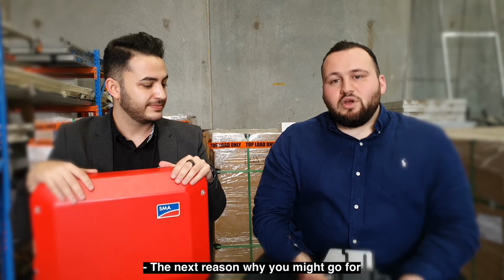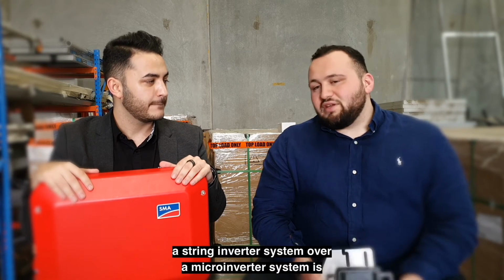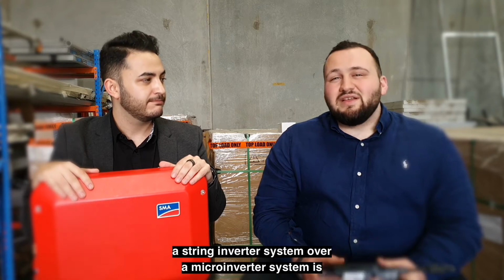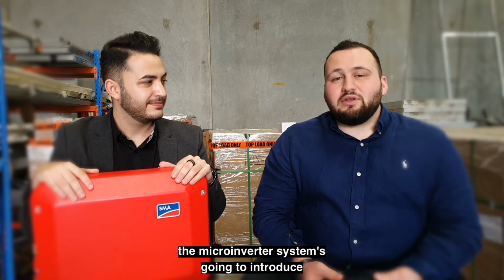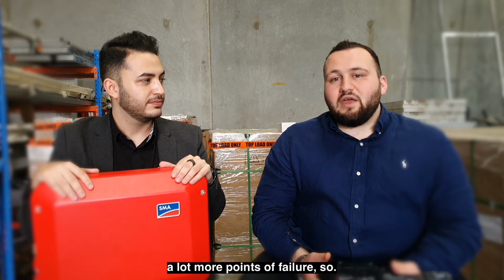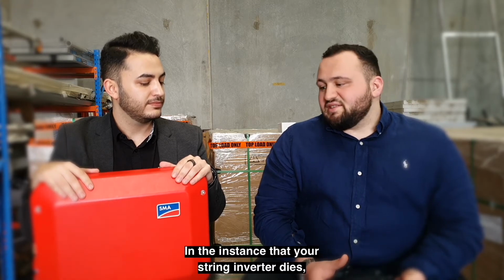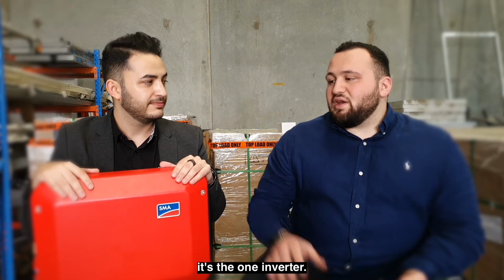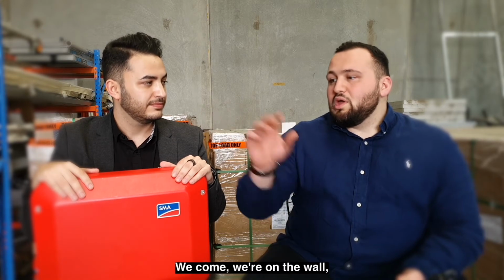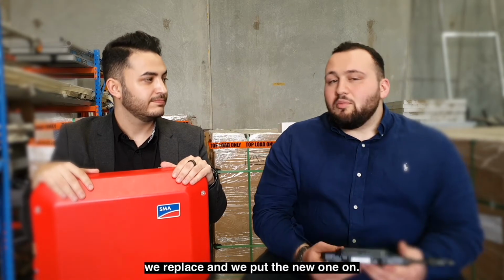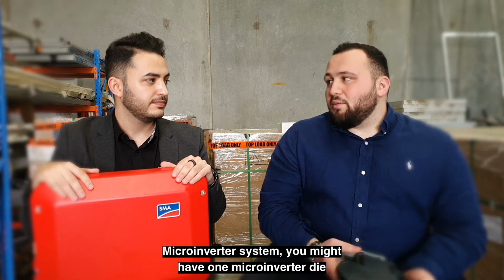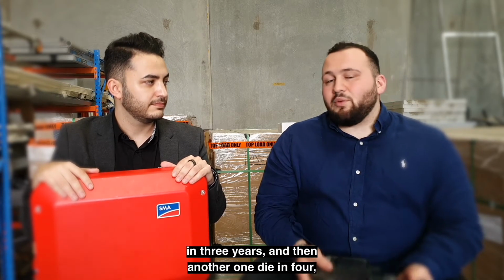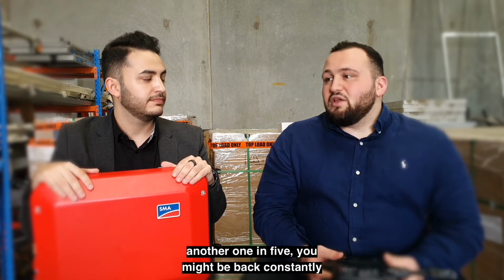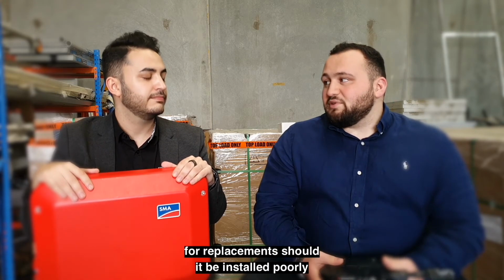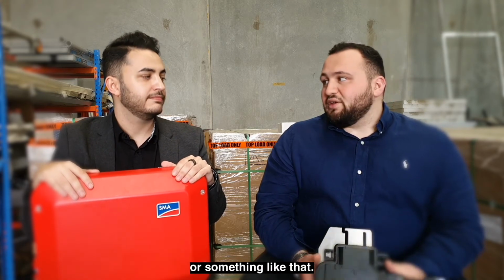The next reason you might go for a string inverter system over a microinverter system is that the microinverter system is going to introduce a lot more points of failure. In the instance that your string inverter dies, it's the one inverter on the wall, we replace it and put the new one on. With a microinverter system, you might have one microinverter die in 3 years and then another one die in 4, another one in 5. You might be back constantly for replacements should it be installed poorly or something like that.